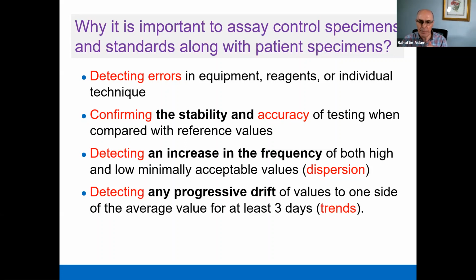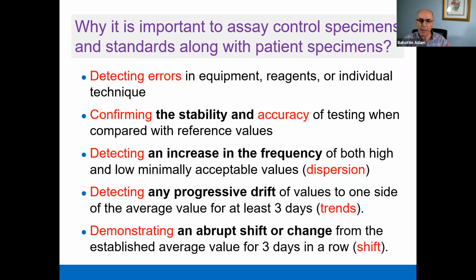And detecting any progressive drift of the value to one side of the average value for at least 3 days, which we call trends, I am going to discuss with you, and demonstrating an abrupt shift or change from the established average value for 3 days in a row, which we call shift.